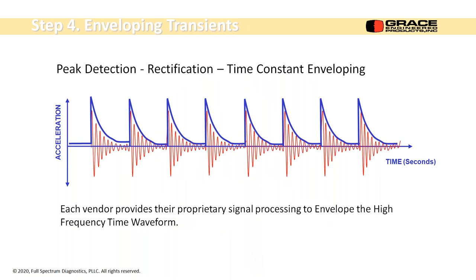Okay. We get these transients, or this string of transients, and it's very low amplitude, and they're all spaced out in time, so we have to zoom in on them. We can put it through some type of software peak detection, something called rectification, where we can eliminate or multiply it so it looks like a bigger peak. And there's another thing called time constant enveloping, which is the blue line right here. So we're drawing an outline of the pulsing of that. What we really care about is that peak event. Okay, so each vendor has proprietary signal processing to do just this. And this would be something that Grace would develop in the coming months.